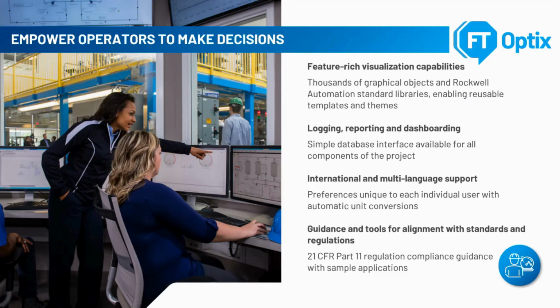Now, in terms of other additional capabilities, Optix can do data logging, of course. It could be either embedded data logging to the local storage of the hardware, or it could be remote data logging. It could be to a remote SQL server over the ODBC protocol, or it could be a remote InfluxDB database. You can also do some lightweight reporting in Optix. Optix has a built-in reporting editor where you can create simple reports that you can have it automatically print out according to a schedule or automatically email to persons of interest according to a schedule.